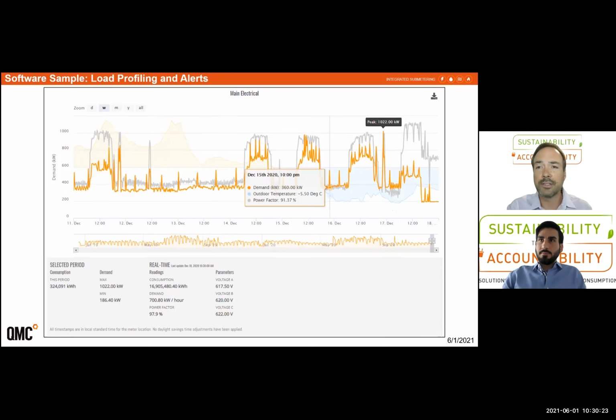This is an example at the same level of an electrical meter. We zoomed in a little bit closer here to a 1 week period. Again, you're seeing that weather overlay. This gray line is reflecting power factor, and you can see real-time amperage and voltage of the system and power factor below as well. So again, if you've set up the meter system correctly to pull all that data back into a more advanced system, you can do a lot of analysis of your loads from one spot. So you can ensure that your voltages, as an example, are where they're supposed to be. Again, these ones are running what seems to be a little bit high.